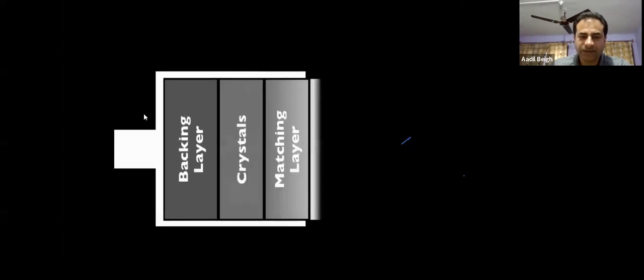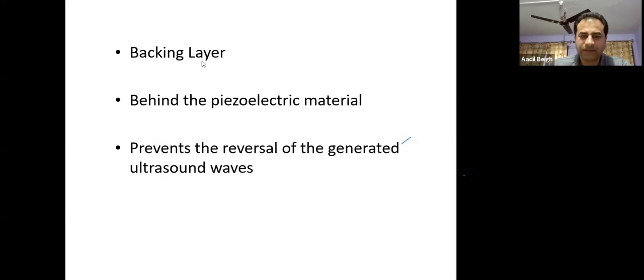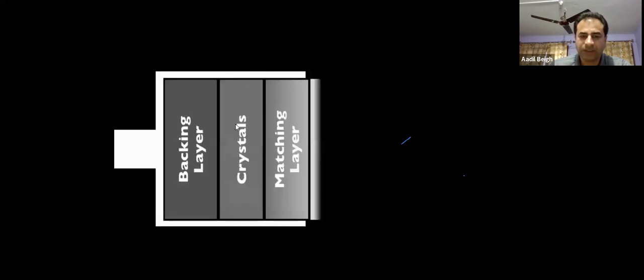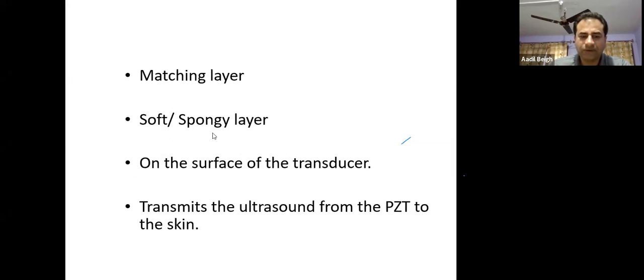So it's like this. This is the casing of the probe. There's a backing layer, there's a crystal, the piezoelectric material, and the matching layer. The matching layer is the blue layer you see on the probe, and behind the crystal is the backing layer. The backing layer is behind the piezoelectric material because it prevents the reversal of the generated sound waves. Sound waves produced by this, some go here, some go here, some go here, so it streamlines them to only one side. The backing layer is for that. The matching layer is a soft, spongy layer on the surface of the transducer. It transmits the sound waves from the piezoelectric material to the skin.